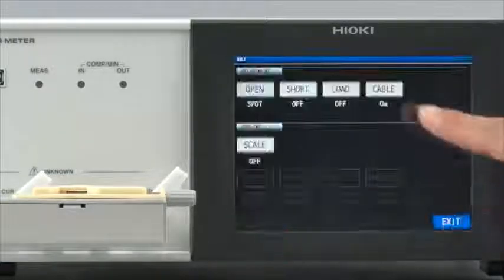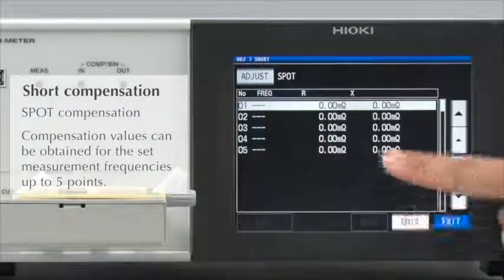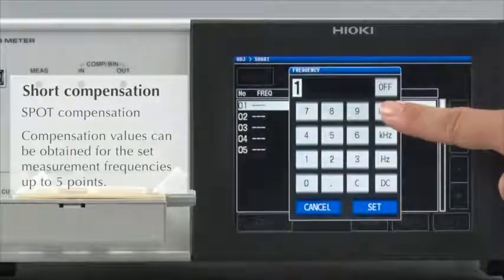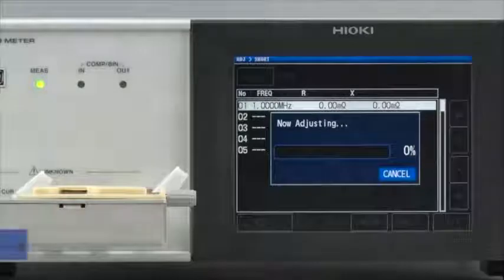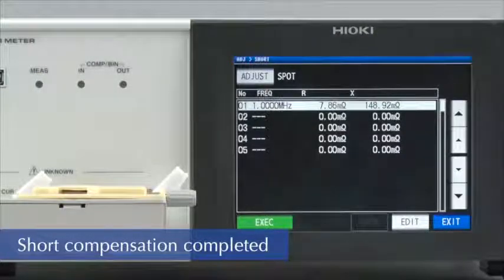Next, conduct short compensation in the same way. Set at 1 MHz. Short the fixture and then conduct compensation. Short compensation is now completed. Let's start testing.